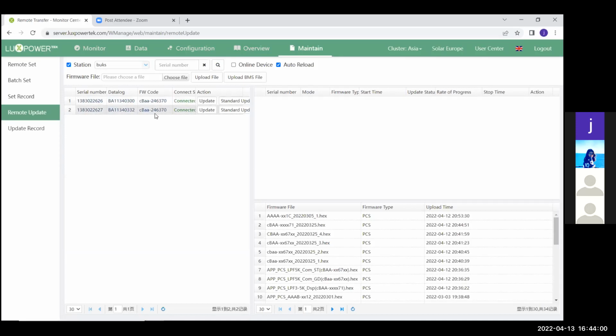This client is on the newest one, 246370. So his inverters are on the newest firmware that's available. Now, for you to update the system, you'll press the standard update button here. As soon as you select the standard update, your machine will show you on this side that it's starting to update. So that's basically all you have to do: click your standard update and it will start to update. If it's on the newest firmware, you can press the standard update button the whole time, and it won't show you the update happening on that side.